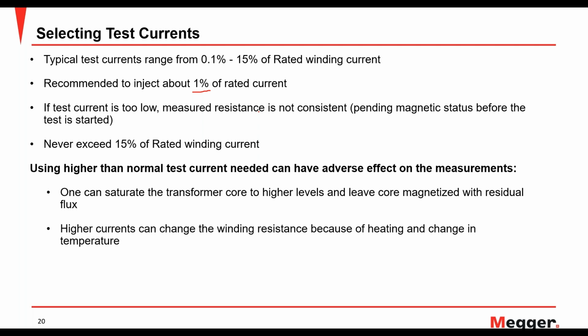Now, if the test current is too low, then the measured resistance is not consistent, depending on the magnetic status before the test started, of course. And we are never to exceed 15% of rated winding current. The reason being, when you do that, there can be residual magnetism in the transformer core that can leave it magnetized. And when you inject AC, it can create some disbalance in the transformer, or it can create heating in the winding and keep changing the resistance. So that's why it's advised never to exceed 15% of rated current.